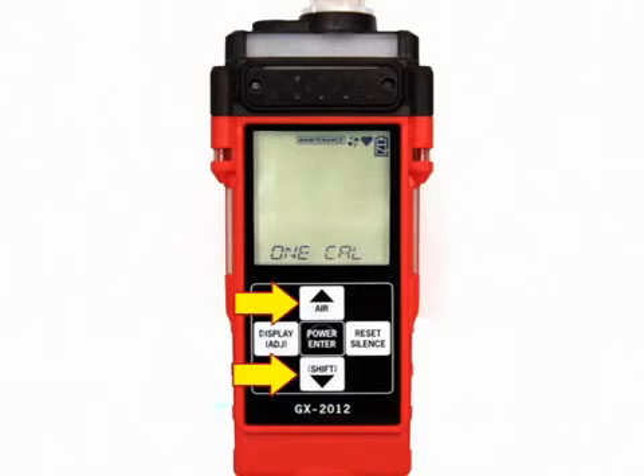Use the air or shift button to move through the calibration mode until 1 cal is displayed. Press and release the power enter button. A channel selection screen appears that displays the CH4 channel. Scroll through the channels using the air or shift button until a channel you want to span adjust is displayed. If you have a 5-sensor unit, the percent volume combustible gas channel will be one of the choices.